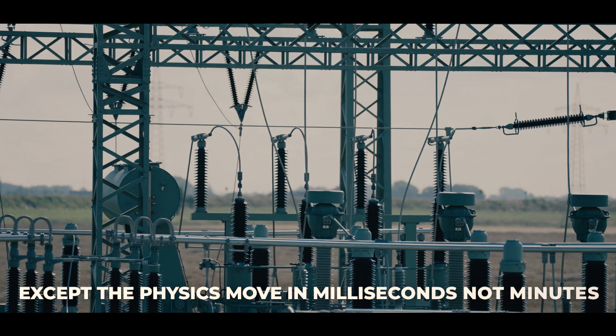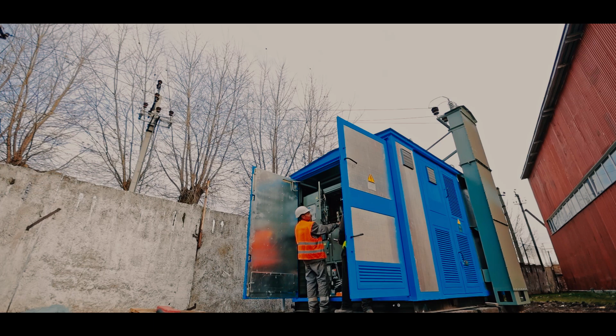When a transmission line trips, the electricity it was carrying reroutes instantly across every available parallel path, not by operator decision, by the laws of electrical circuits. Those parallel paths were not designed to carry the additional load. They heat, resistance increases, heat builds further. Protection circuits trip automatically. Now 2 lines are offline. The load reroutes again. 3 lines of electricity are moving through an infrastructure rated for 1.